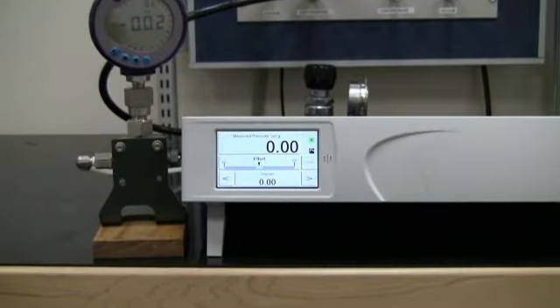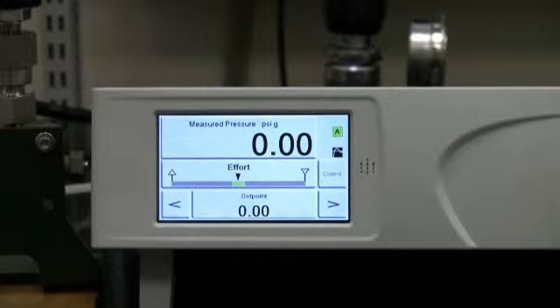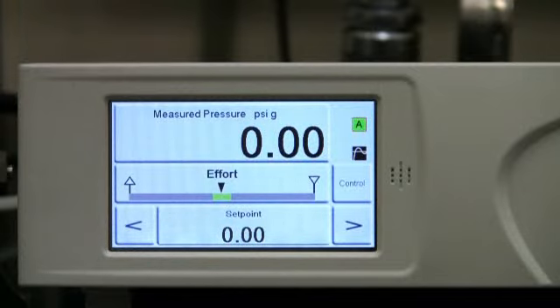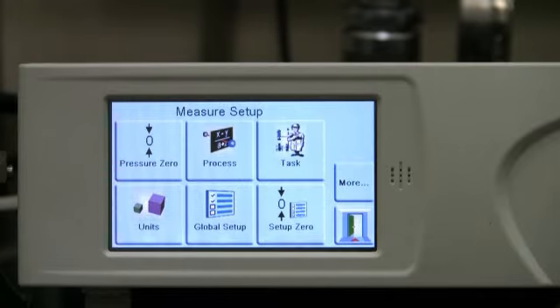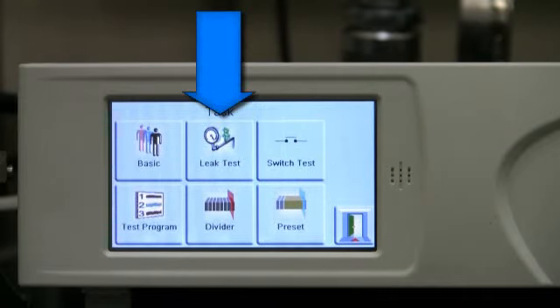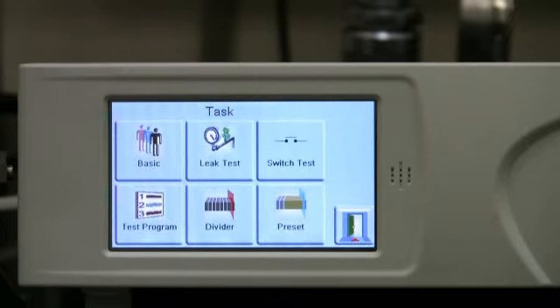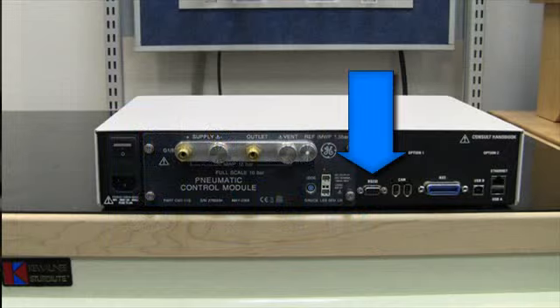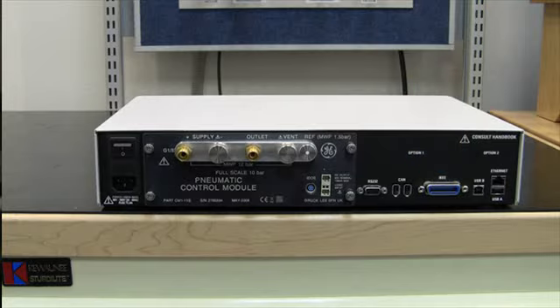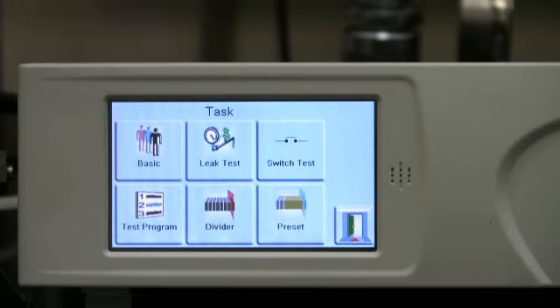PACE5000 includes a variety of built-in features to make the process of performing different pressure calibration tasks easier. So far, we have been operating in basic mode where we enter the set point value one point at a time. Alternatively, we can select from various other tasks such as performing a leak test, calibrating a pressure switch, test program, which we'll review in a minute, divider, which allows us to select a minimum and maximum pressure with evenly spaced intervals, and the preset that allows us to assign a custom sequence of pressure values that may not be evenly divided.